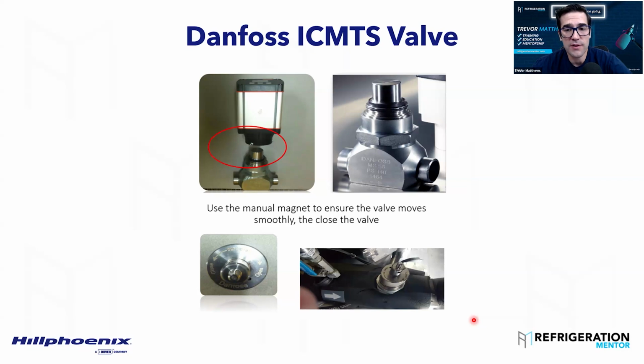But you never want to take off really any valve controller and let it run, because now the valve itself doesn't know where it's actually positioned. So if you ever pulled this off and it's still adjusting or moving, and it moves to 100% open, and you put it on, but it's not really 100% open, it's going to not know its position. This goes with really any valve manufacturer. So just make sure you don't do that. And if you do, you got to recalibrate it. Make sure it goes home and it's 100% closed.